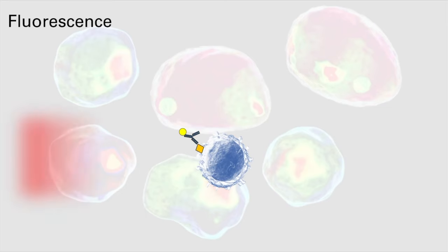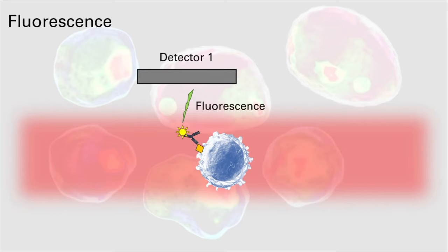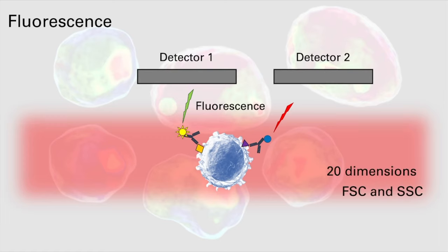That antibody is then labeled with a fluorochrome which when it passes through a laser beam is excited and emits light at a different wavelength that can be picked up by a detector that is specific to the wavelength of that emitted light. The number of different fluorochromes that can be used is largely determined by the number of lasers and the number of different detectors that the flow cytometer possesses. Modern flow cytometers allow users to interrogate a cell in 20 different dimensions, forward scatter, side scatter and 18 fluorescent channels which requires four different lasers emitting light at different wavelengths. The boundaries are continually being pushed.